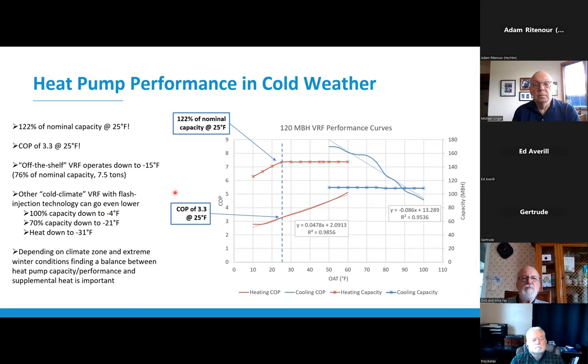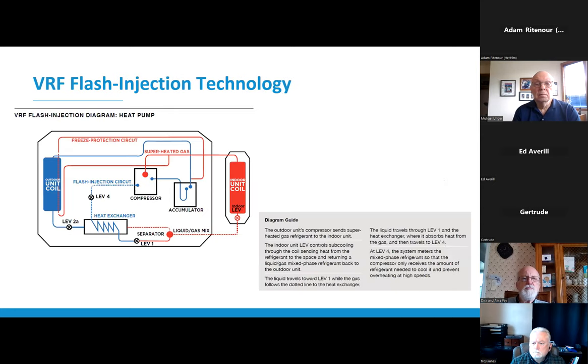In the next slide, I'll talk about what this VRF flash injection technology is that's helping these cold climate units. So this is what a VRF flash injection technology circuitry might look like. Ironically enough, the hangup with cold climate is that the compressors start overheating in these VRF systems. So what we need to do is have this flash injection circuit which delivers refrigerant over to the compressor to cool it, because it's working so hard in those super cold climates. And because of this flash injection technology, this compressor is able to continue running and to perform in those colder climates.